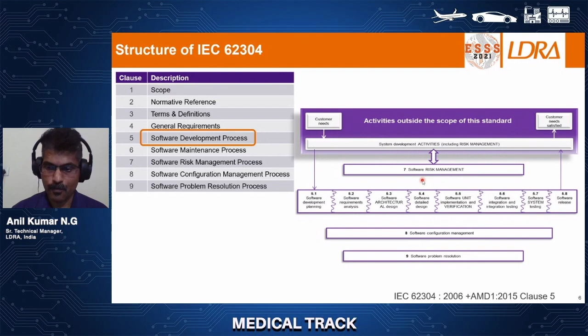Now let's see what the different software safety classifications are in IEC 62304. The standard expects the manufacturer to assign a safety class to the software system as a whole. This classification is based on the potential to create a hazard that could result in an injury to the user, patient, or the person who is actually using that equipment. A software system may have a lower worst-case risk than the device overall, but cannot be on a higher side. The default assumption is that any device will be classified as class C, and then it will be categorized based on various risks and hazards. We'll discuss that in a while.